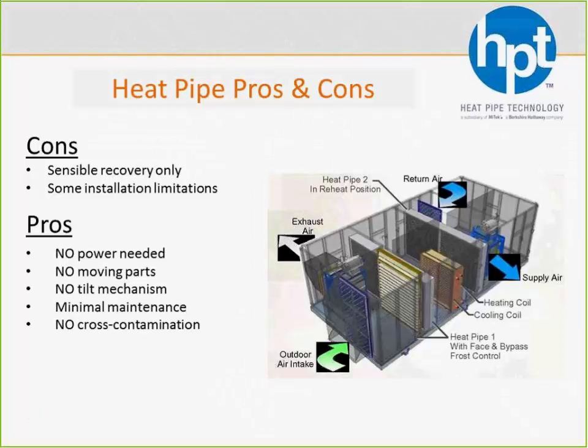Plenty of pros, though. The fact that we only need a delta T to operate means we don't need any power, we don't have any moving parts, and again, like I said earlier, we don't need a tilt mechanism. So from a maintenance standpoint, there's hardly any maintenance involved with a heat pipe. We get a lot of jobs because we're very maintenance friendly, and the owner just wants something that they can kind of set it and forget it. The maintenance for a heat pipe is clean it. We recommend cleaning it whenever you clean the coils, and you'll be good to go. That's really all that's involved.